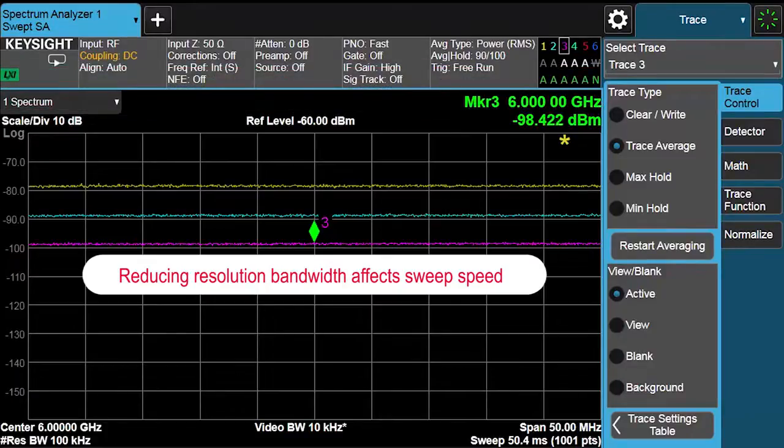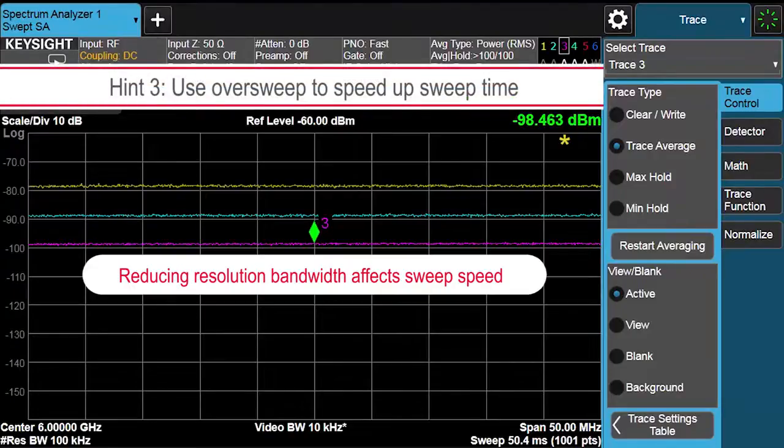Often, when you're looking for low-level spurs, it is necessary to balance the trade-offs between sweep speed and your displayed average noise level. The new fast sweep feature in the EXA allows you to lower your RBW, thus lowering your noise floor while still sweeping quickly.